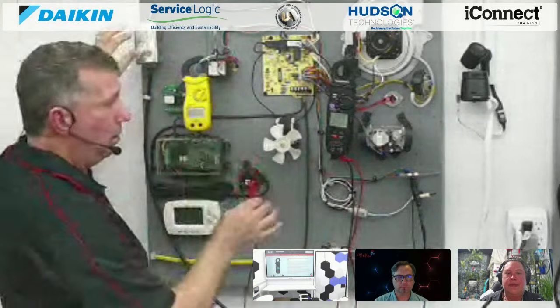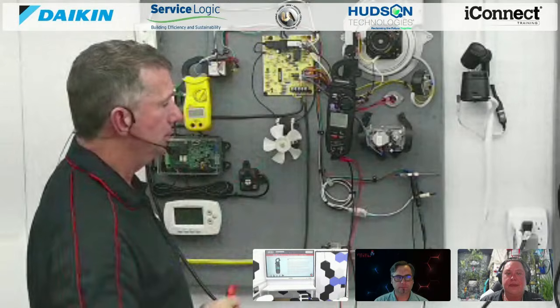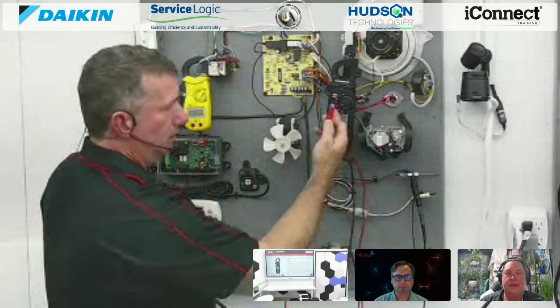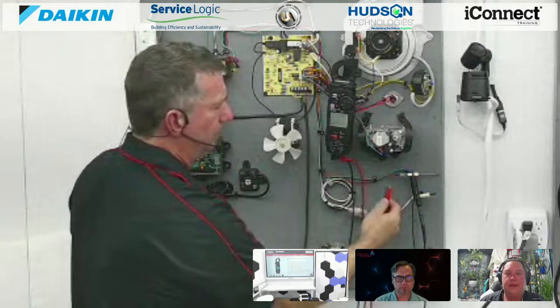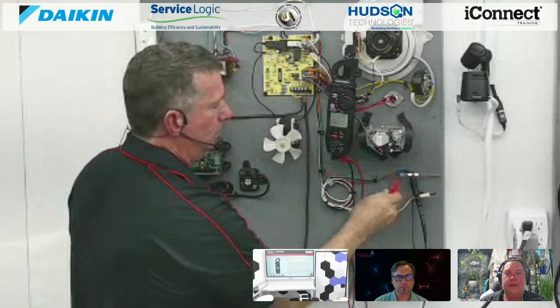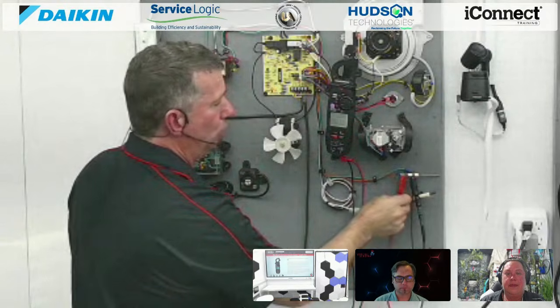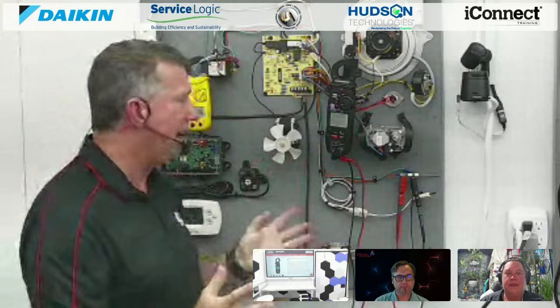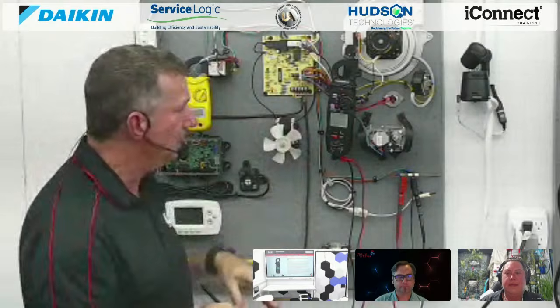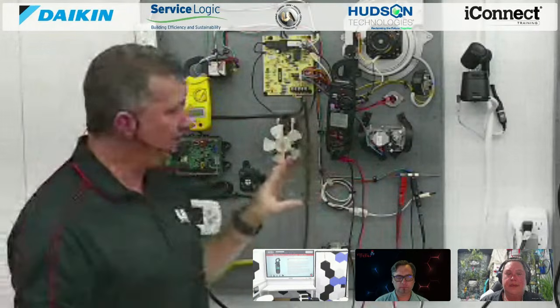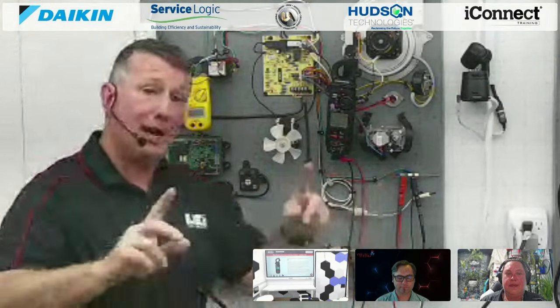So on all of our modern ignition boards, putting our meter just on plain old volts AC, from ground to that flame rod, it's typically between 40 and 80 volts AC. On some of our commercial industrial applications, I've seen higher voltages, but that's pretty typical. So we're actually applying AC voltage directly onto that rod. It doesn't have anywhere to go, right? Well, it's going to try to make its way to ground.